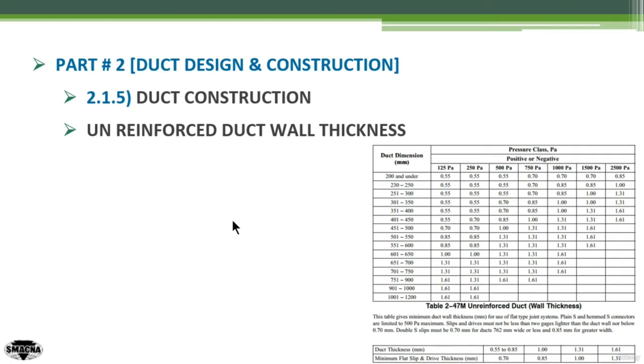Since a duct has two dimensions — width and height — and the width is usually larger, you always take the largest dimension. For example, for a duct of 70 cm width by 30 cm height, you take the 70 cm dimension and use it as the input in the first column.